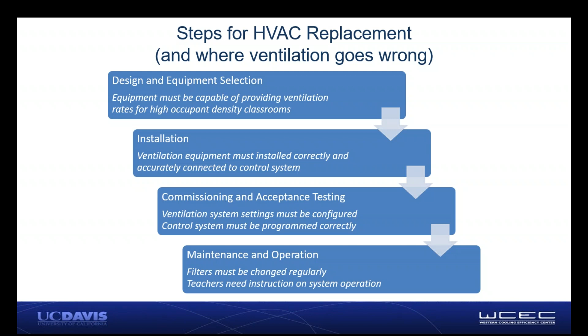Step two, you have to make sure your ventilation equipment is installed correctly and accurately connected to the control system, meaning essentially that all the wires are connected in the right place. The third step is commissioning and acceptance testing, and this is kind of your fail-safe. At the end of the day, once the system is all installed, and I'll talk more about this, acceptance testing is required so that you set the ventilation system settings to make sure they're delivering enough air, and then you measure it. And lastly, you have to maintain and operate the system, so filters must be changed regularly, and teachers need some instructions on how the system works as well. Okay, next slide.